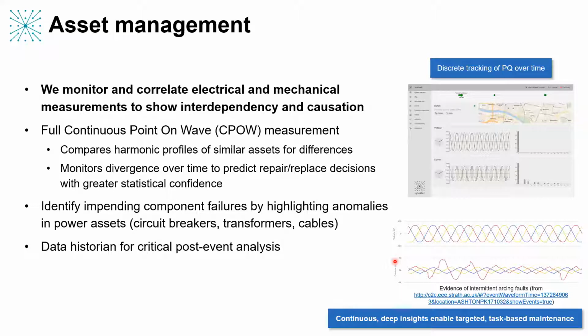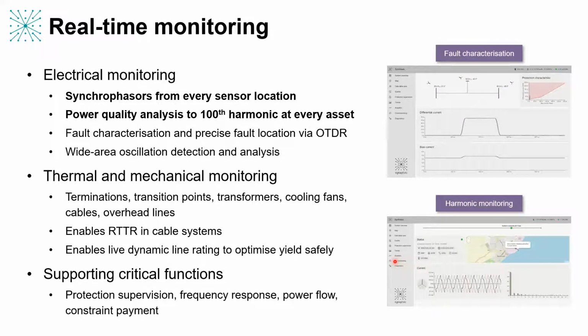And then a couple of questions have come up about how our technology will apply to monitoring cables. Some people are talking subsea, some people are talking underground, of course. So it might be good if you could talk about anticipation or prediction of failure, because we were talking about power quality in one section and the fact that you could see certain harmonics which might be harmful, according to the academic literature we know about, to the premature aging of cables. But in terms of our ability to monitor particular locations, terminations come to mind for me. To what extent can we predict cable failures and look ahead, rather than the protection response to a fault once it has occurred?